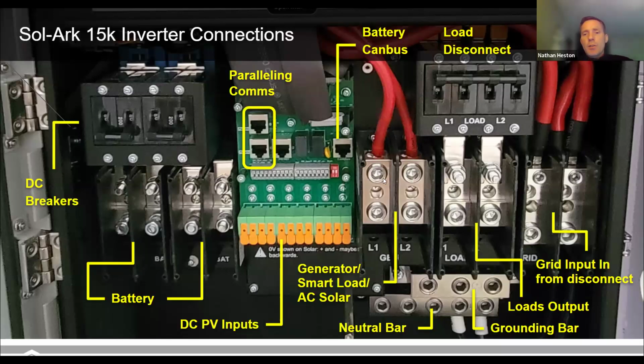And then this is the generator input. The grounding bar is up here, and then you've got a neutral bar, common neutral bar on the bottom for split phase applications. And then the load output is here. You do have a disconnect on that load. And then the grid input here, you can accommodate up to 4-aught aluminum or 3-aught copper is typically used for your connections on 200 amp service.